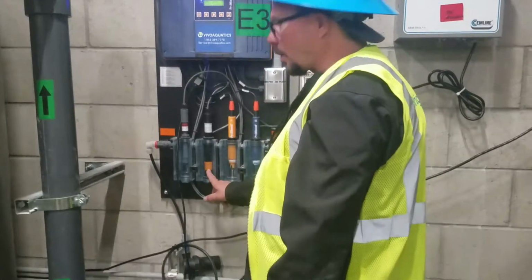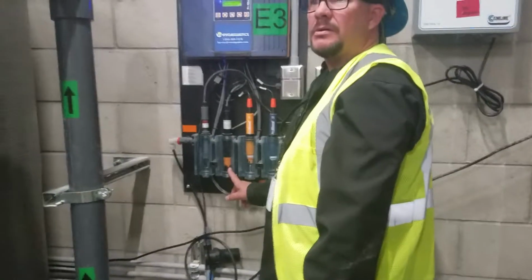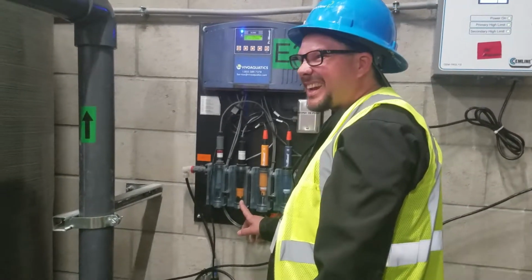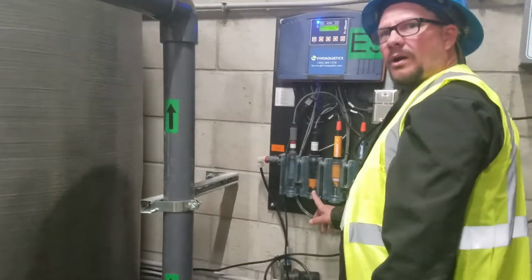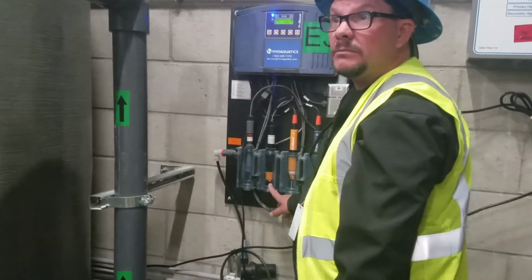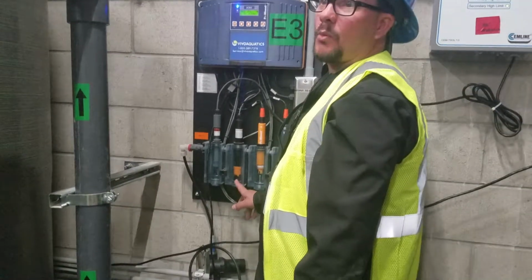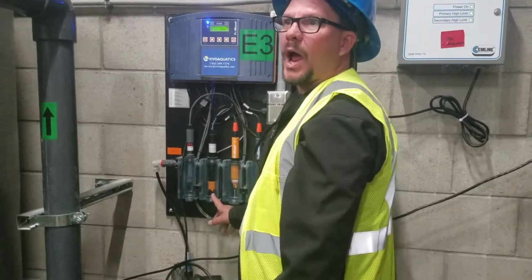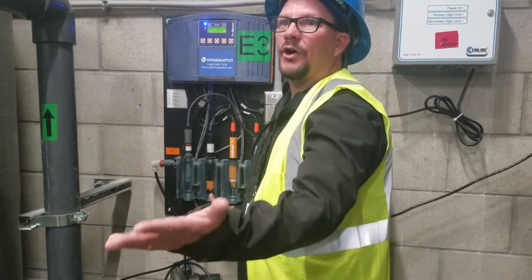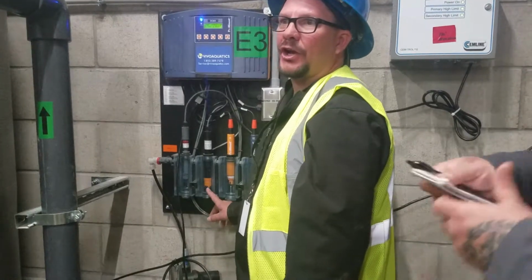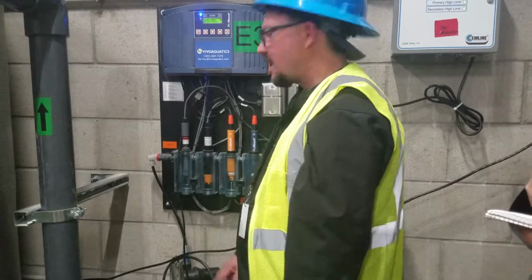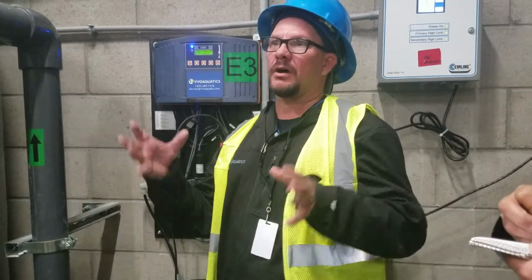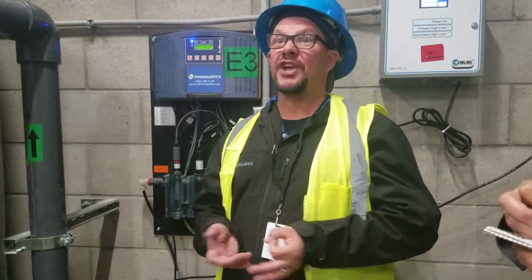This probe here is a gelled probe. This is something that we need to maintain, probably quarterly? Typically quarterly is a good check, or if there's a mishap. If there's a mishap, we're going to want to go here. The first thing you're going to see is your chlorine went way out of whack for who knows what reason. Generally, you're going to go right to this cap. That cap's removable, it has a gel in there. I can give a one-on-one or a group class on how to re-gel a probe.